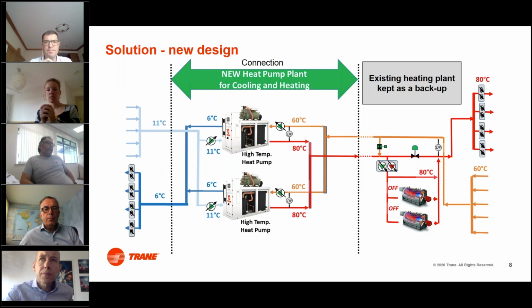So we removed the disconnection. So we connected the dots of the heating and the cooling by a water-to-water heat pump system. In this case, it's a parallel system. Many times we also use a serial connection. And by using this system, we were able to provide the cooling at 6 degrees and the heating at 80 degrees with one and the same system.